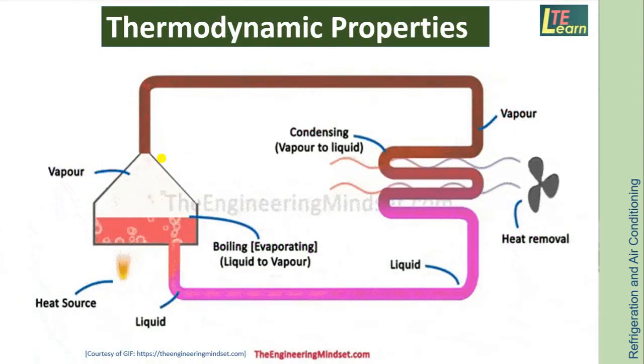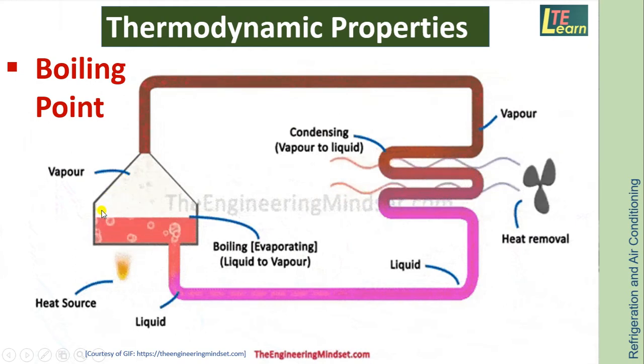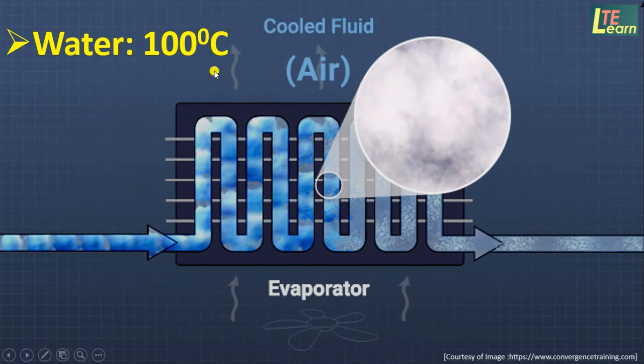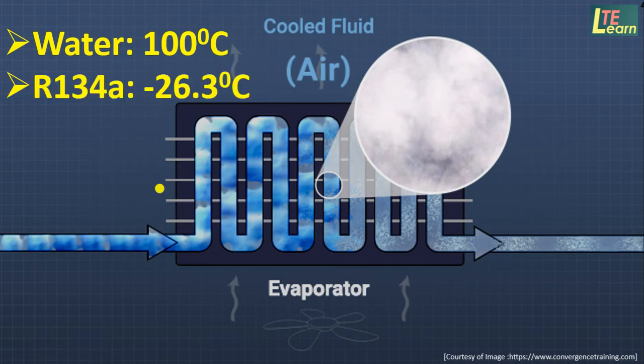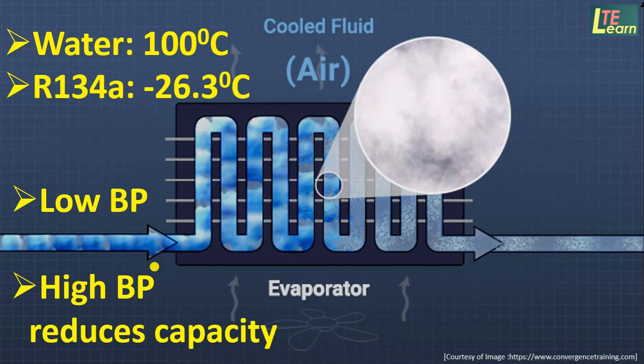Thermodynamic Properties of refrigerant include Boiling Point — the temperature at which liquid refrigerant at the evaporator is converted into vapor by absorbing heat from the space to be cooled. As the boiling point of water is 100°C, it cannot pick heat from the space to be cooled. Hence, refrigerant R134A having a boiling point of -26.3°C is used in a domestic refrigerator. Boiling point of refrigerant should be low, as a high boiling point reduces the capacity of the system.